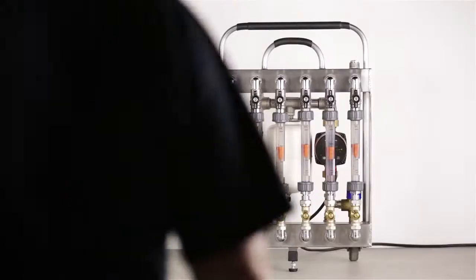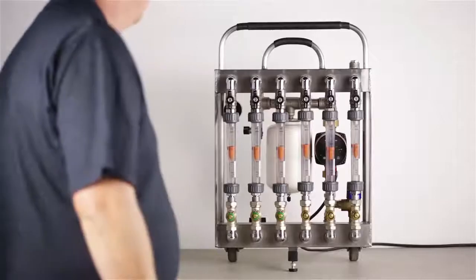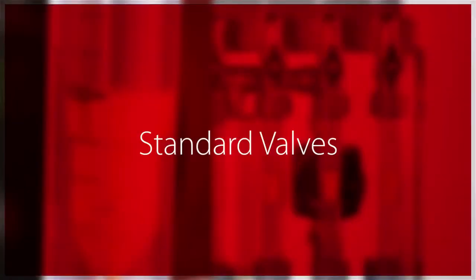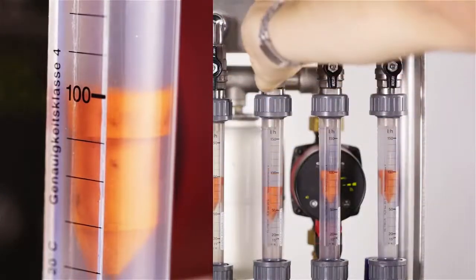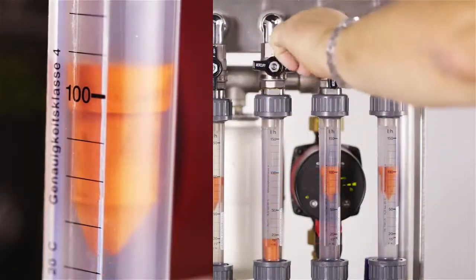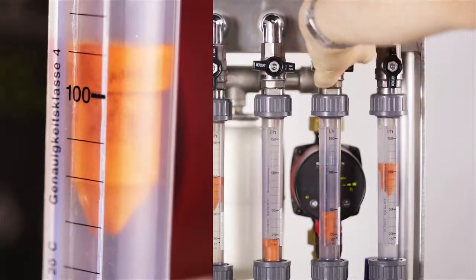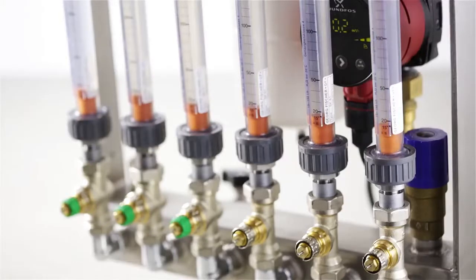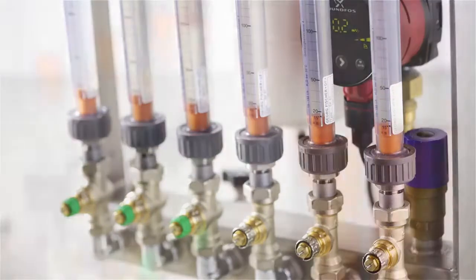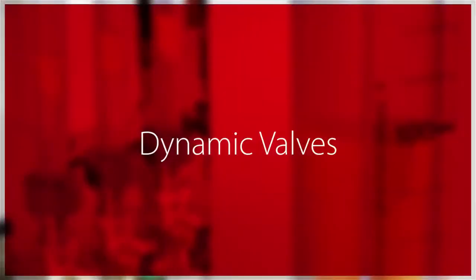So let's see what happens if, for example, the sun rises and starts beating down on one part of our imaginary building. The thermostats on the sunny side will shut down, resulting in excessive flow on the side where the standard radiator valves are installed. Compare this situation with the dynamic valve, you can see that there is no change in the flow.